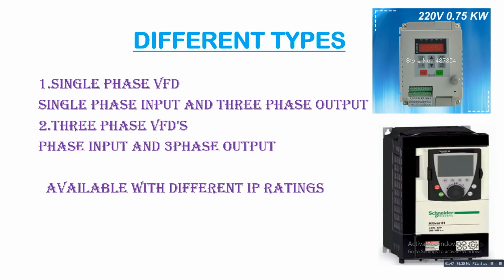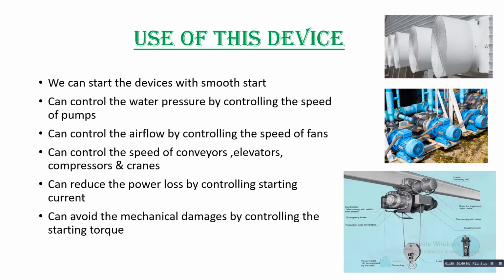So what is the use of this device? Why and where do we have to use it? We can start our equipment with a smooth start. Usually, if you start a motor-connected device, like fans, pumps, cranes or conveyors, with a DOL or star delta starter, there will be high starting current or high starting torque, so there won't be a smooth start. By using this VFD you can do a smooth start.